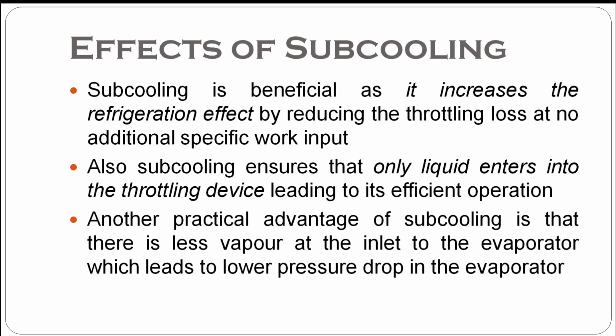Now let us see the effects of subcooling and superheating. Subcooling is beneficial as it increases the refrigeration effect by reducing the throttling loss. It reduces the throttling loss. Also, subcooling ensures that only liquid enters the expansion device. Another third advantage is that there is less vapor at the inlet to the evaporator, which leads to lower pressure drop in the evaporator.